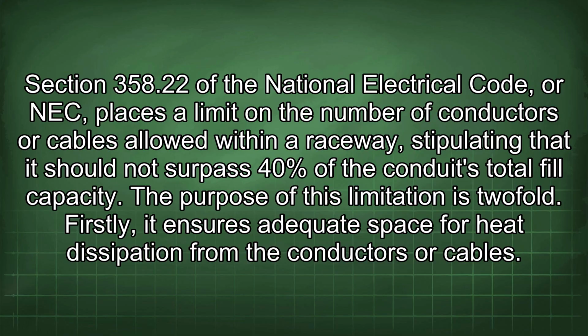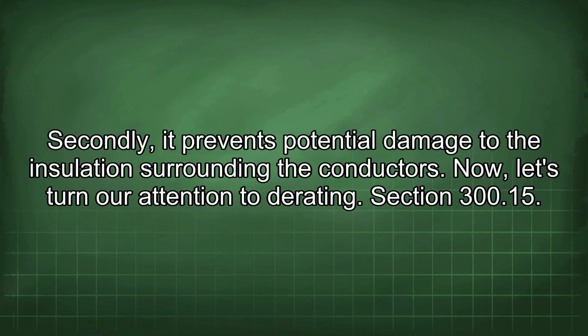Section 358.22 of the National Electrical Code, or NEC, places a limit on the number of conductors or cables allowed within a raceway, stipulating that it should not surpass 40% of the conduit's total fill capacity. The purpose of this limitation is twofold. Firstly, it ensures adequate space for heat dissipation from the conductors or cables. Secondly, it prevents potential damage to the insulation surrounding the conductors.